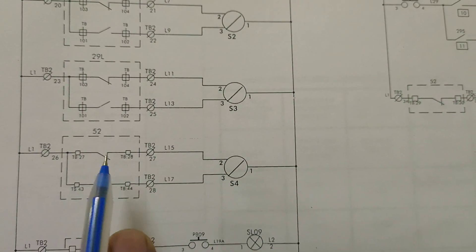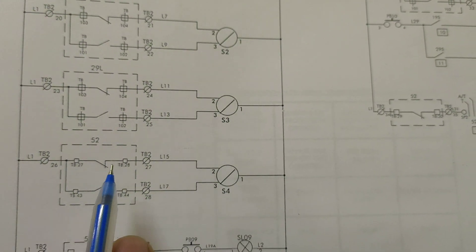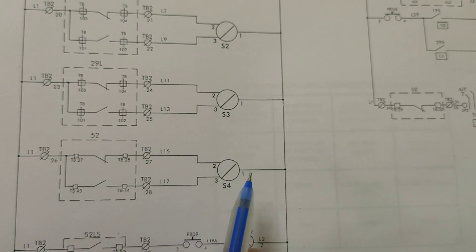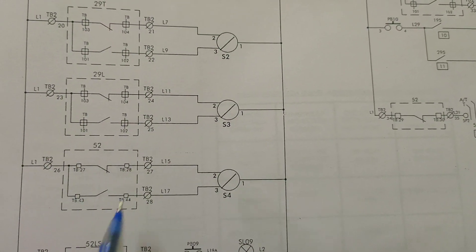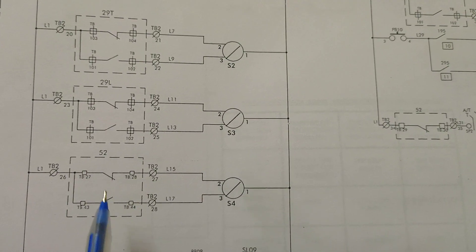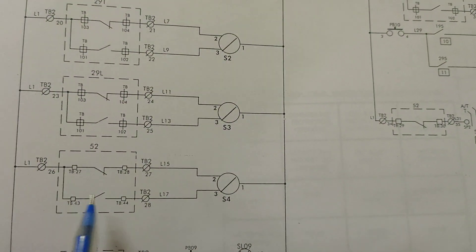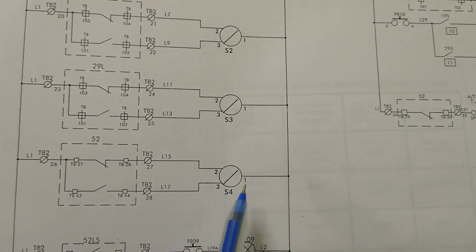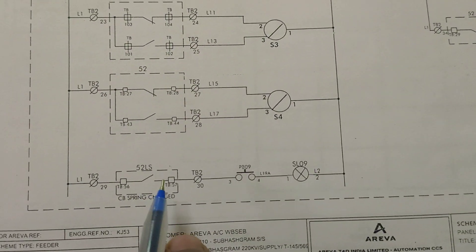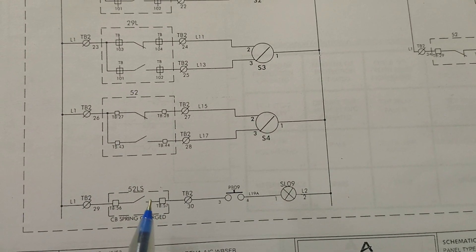52 — we know that 52 is the breaker contact. The breaker semaphore shows when the breaker is in ON or OFF conditions. When we switch on the breaker, the auxiliary contact position is changed — the NC contact becomes the NO contact — and DC passes through, and the semaphore operates and goes to the ON position. We can confirm that the breaker has been closed successfully.